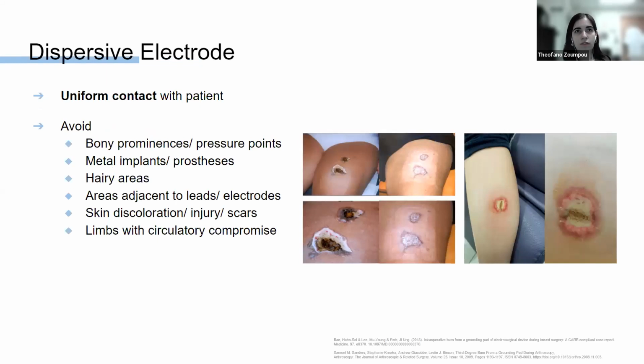So the dispersive electrode is a part of the monopolar device circuits. And in order for it to function properly, it must be in uniform contact with a large surface area of tissue, and the tissue has to be of low impedance. This is why we should, in general, avoid places such as bony prominences or prosthesis, scar tissue, or tissue with vascular compromise, among others that you can see here, when deciding where to place the dispersive pad. Because if the dispersive electrode is not placed properly, we run the risk of having uneven current density throughout the application site, and injury can occur. And here you can see pictures from two case reports where the patients suffered burns at the site of the dispersive electrode, and this is something that we don't want to happen.